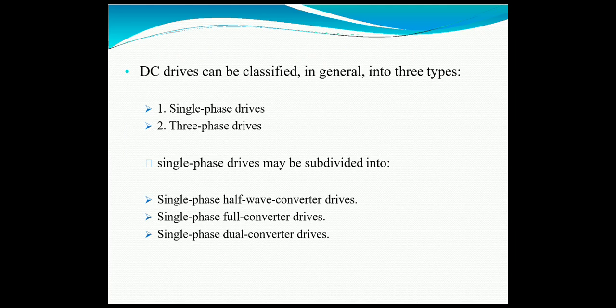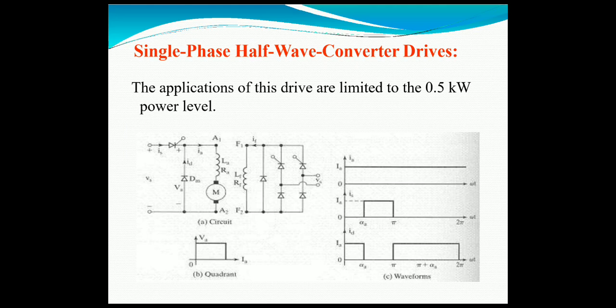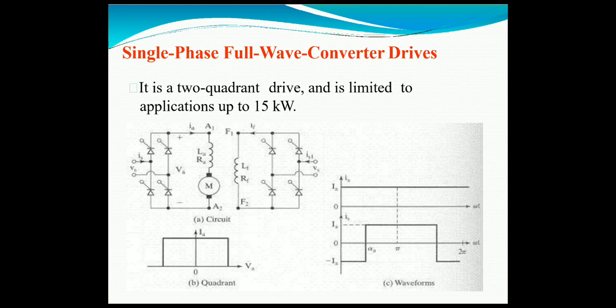In these drives, the AC supply is converted into DC supply with the help of a rectifier section, and the drive is driven with the given supply. The single-phase half converter drive diagram is shown here and will be discussed in upcoming lectures. It operates in the first quadrant only. The single-phase full-wave converter drive is a two-quadrant drive, limited to applications up to 15 kilowatts.